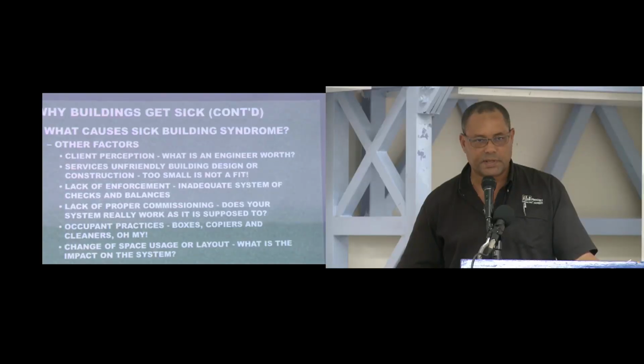If we have a change in the number of persons occupying a space, obviously equipment and usage go down or go up accordingly. Your system may not be designed for that. That's specifically a problem with a speculative building. You have to assume what your load is going to be. And sometimes you get a standard office space that a call center moves into, which has four times the density of what you're normally expecting. So it's hard to accommodate those wide fluctuations in occupancy.